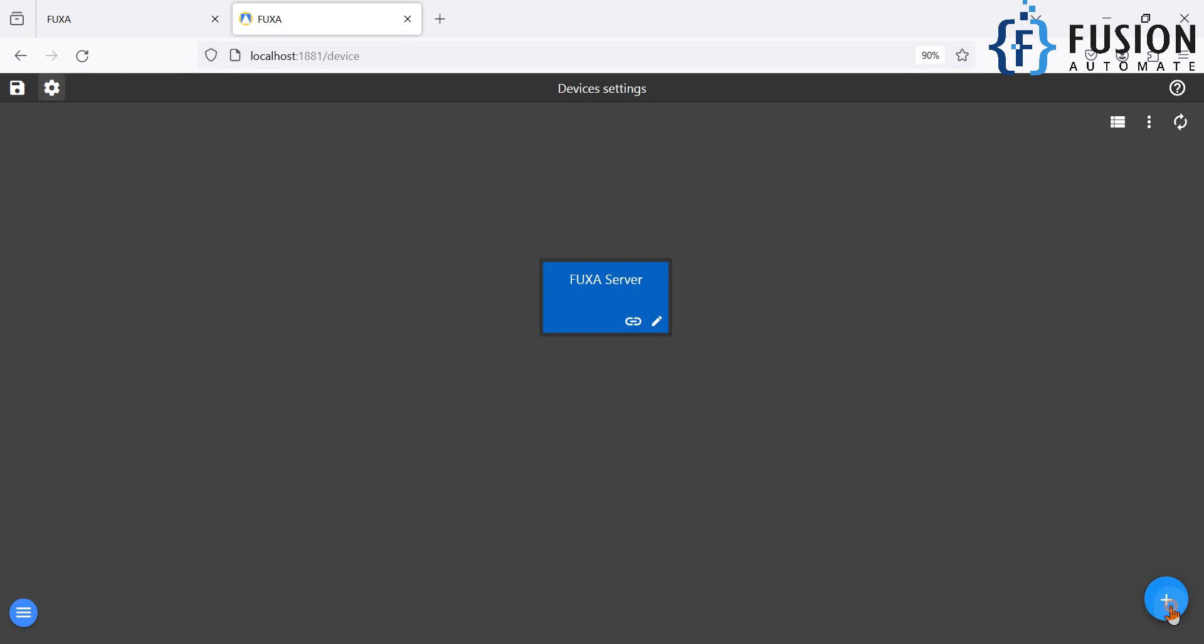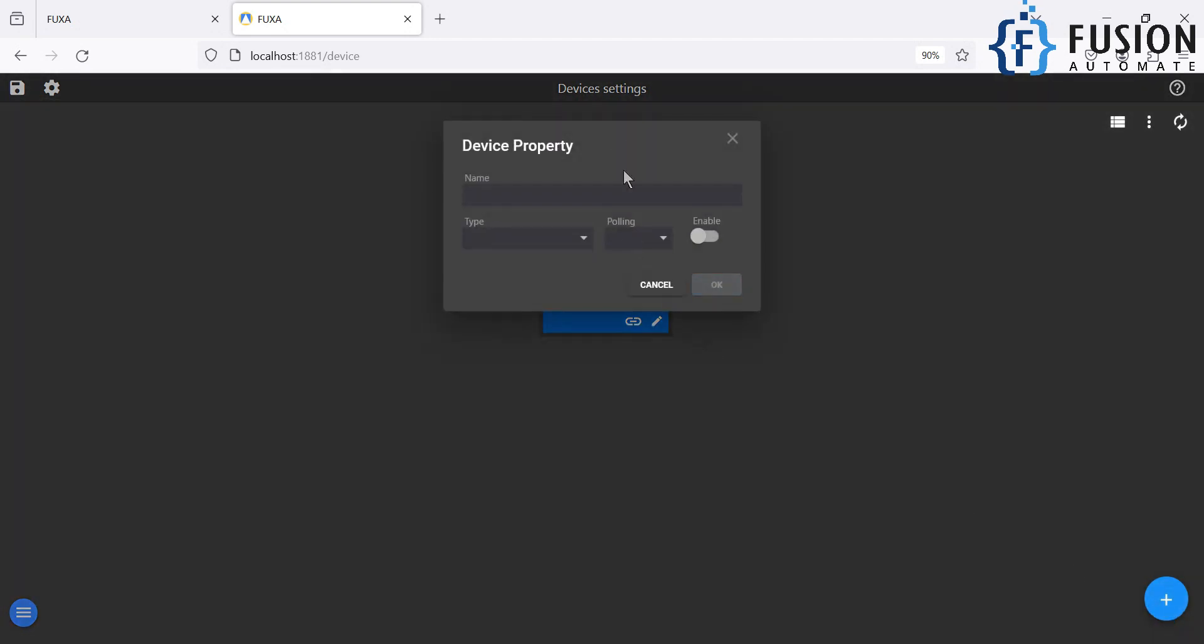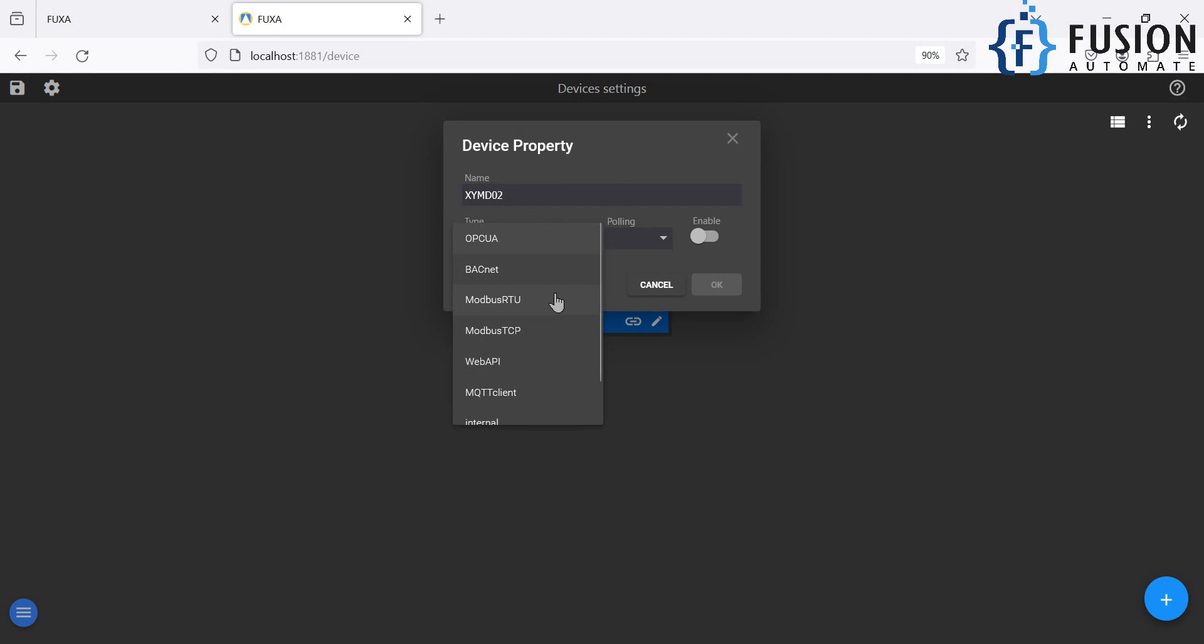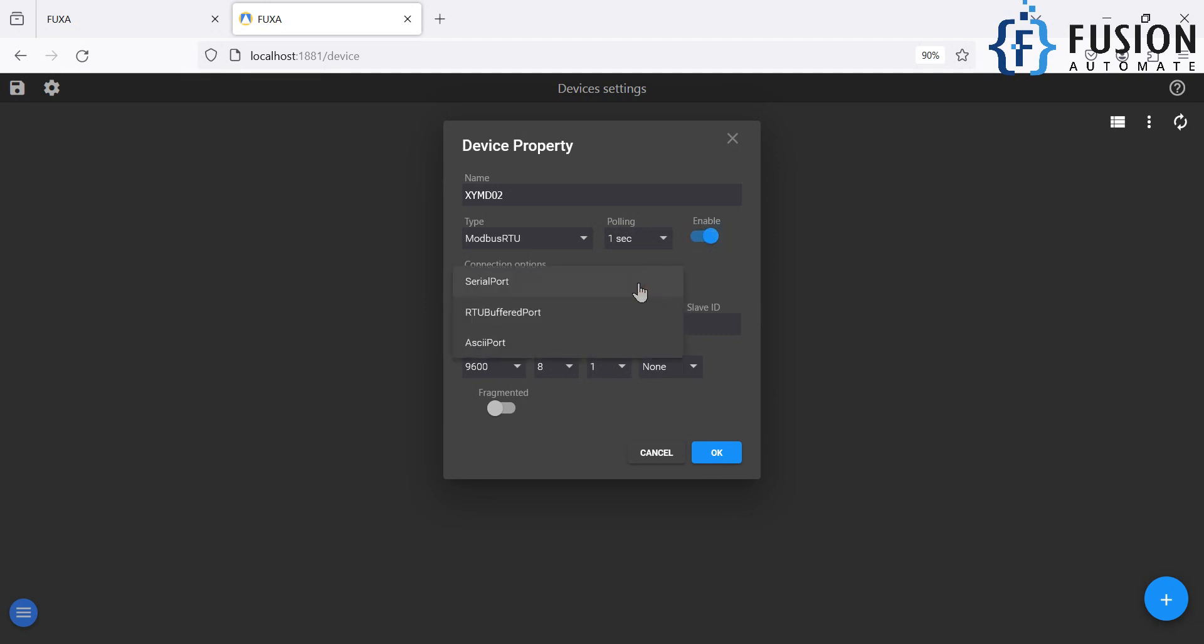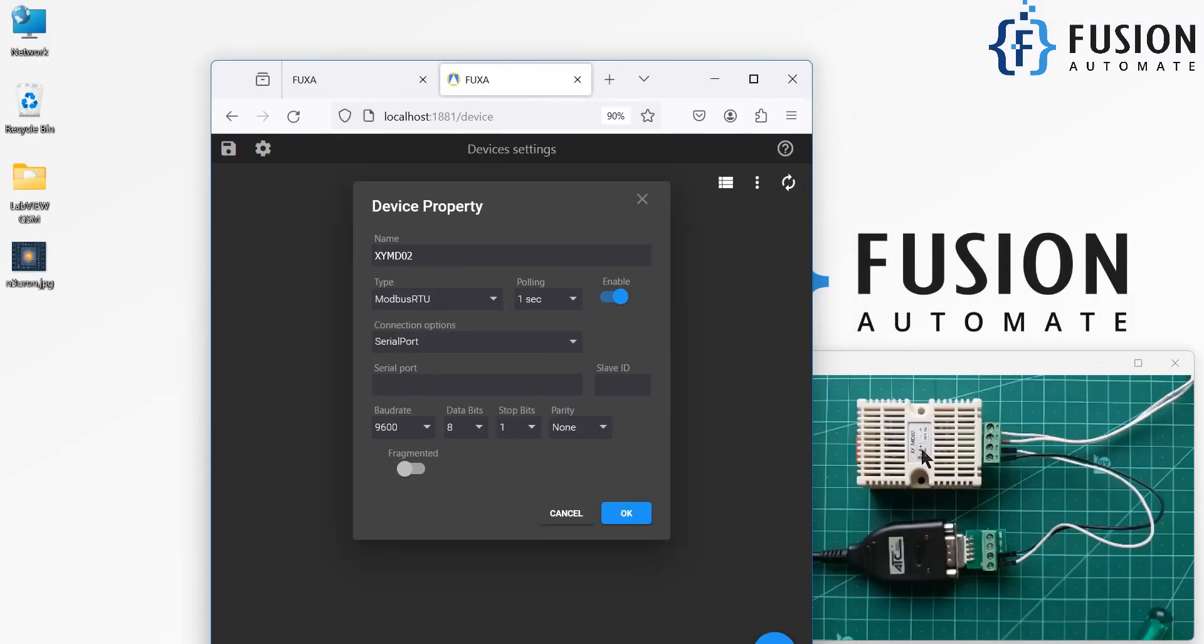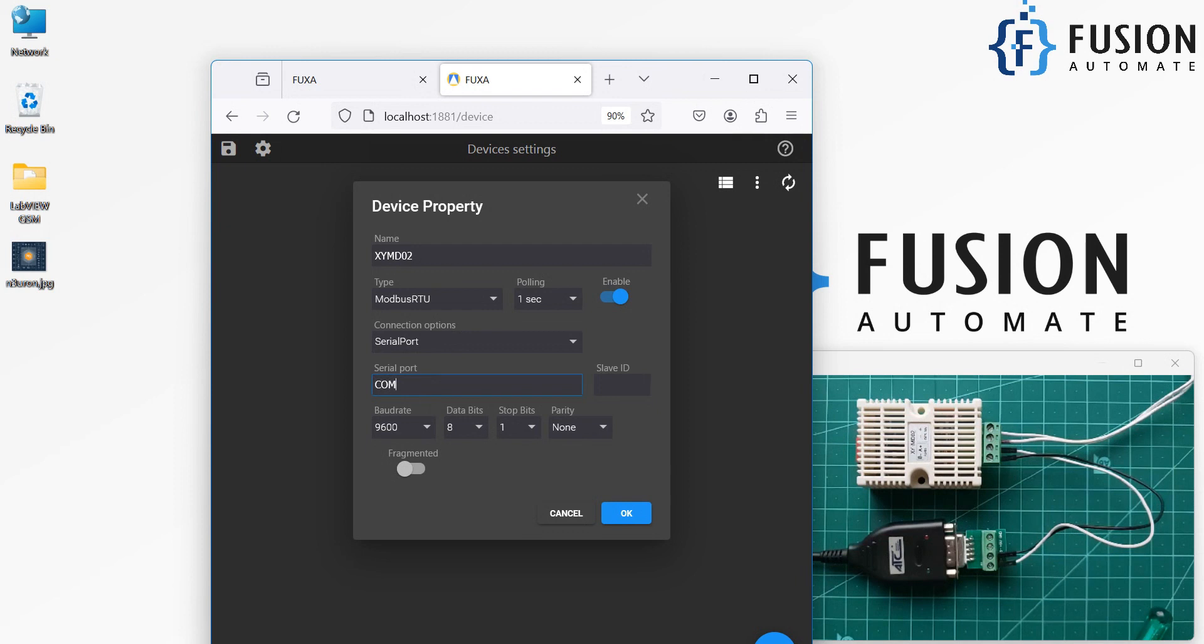So you have to click on this plus icon and our device is XYMD02, which is temperature and humidity transmitter. And the type of this device is Modbus RTU. And we want to poll the data at every second. We are going to enable this device. Connection options: so we are going to connect with device serially on the serial COM port, which is COM7. So I am going to provide COM7 here.